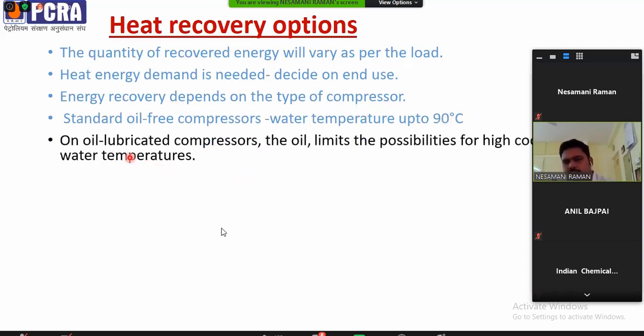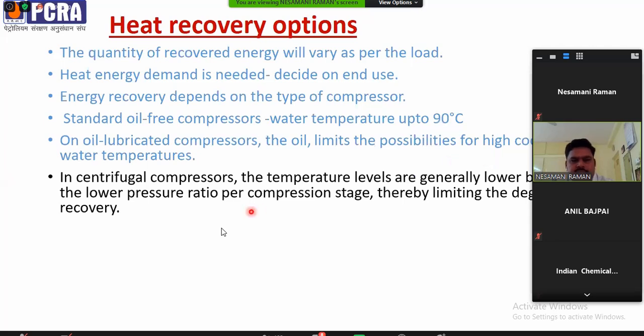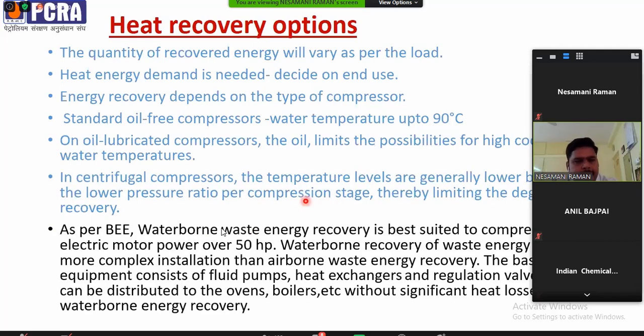If you see oil-lubricated compressors, the oil takes away some heat, so it limits the possibility of heat recovery and the water temperatures. In centrifugal compressors, the temperature levels are generally lower because the pressure ratio in each stage is lesser. So it will limit the degree of heat recovery. Means heat recovery will not be that much.